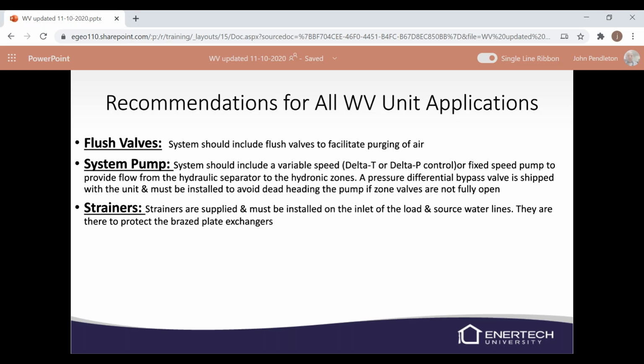If you're using a buffer tank or hydraulic separator between the unit and the loads, we don't need a bypass valve there. If you're not using a buffer tank or a hydraulic separator, then we will need to install the bypass valve in between the unit and your loads to avoid any pump deadheading if your valves don't fully open or something like that. Strainers are shipped with the unit because they're required.